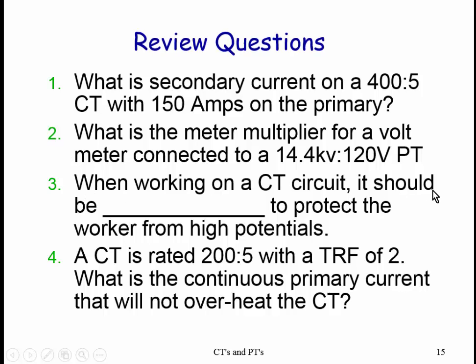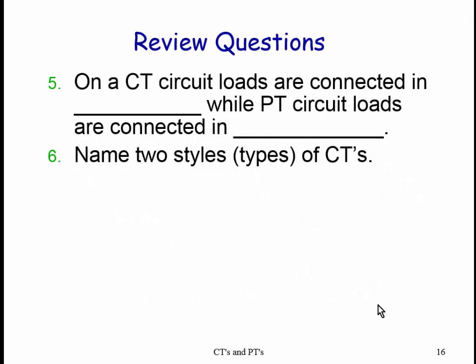When working on a CT circuit, it should be what to protect the worker? If you're going to work on a CT circuit, you short the CT circuit. Let's say you have a CT that's rated at 200 to 5. It has a TRF of 2. TRF is transformer factor. So a 200 to 5 CT, that's the ratio, but that alone doesn't tell you how many amps it's rated for. Stamped on the CT will sometimes have something called a transformer factor, which means if you had 2, then this CT would be rated at 400 amps on the primary and 10 amps on the secondary. And it's all temperature based. They'll in fact even stamp a temperature on there. So that's what that one would be rated for.